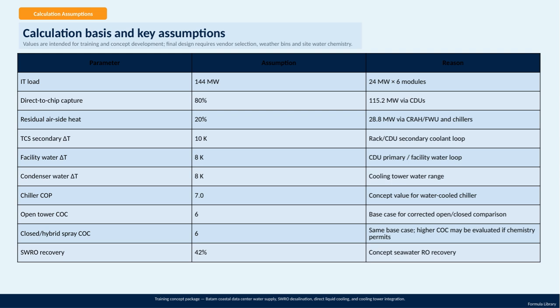We've also assumed specific temperature differentials in various cooling loops: a 10 Kelvin change in the secondary coolant loop between the racks and the cooling distribution units, and an 8 Kelvin differential in both the primary facility water loop and the condenser water for the cooling towers. These values reflect typical operating ranges to optimize heat exchange performance. For the chiller's efficiency, we're using a coefficient of performance of 7.0, which is a concept value typical for water-cooled chillers. The cycles of concentration for the cooling towers is 6, used as a baseline for comparing open, closed, and hybrid cooling approaches. This value might be adjusted higher if water chemistry conditions support it.